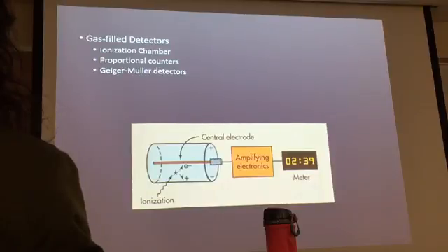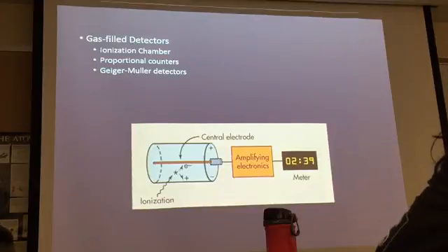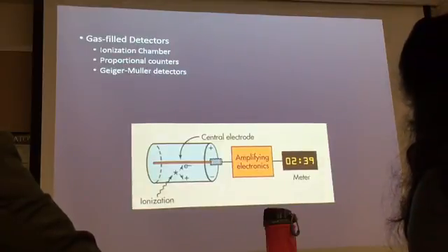So you increase the voltage, and then they become more sensitive to radiation. Being more sensitive doesn't mean that it's accurate. Not the same thing. What it's saying is that yes, you can pick up radiation, but what you're seeing is maybe not very accurate.